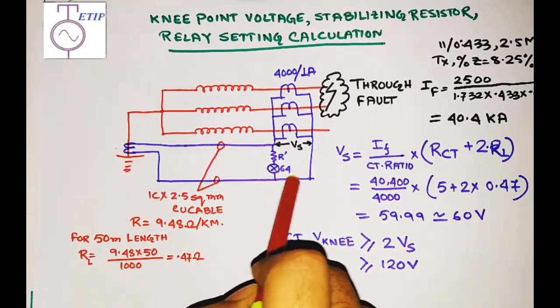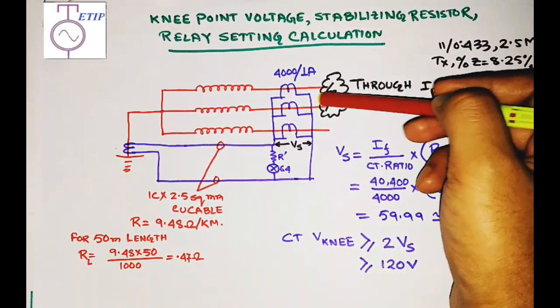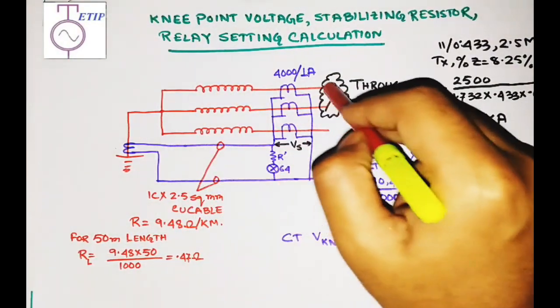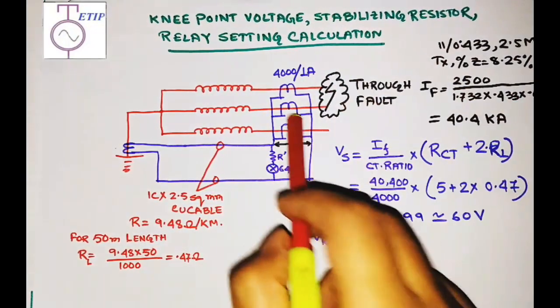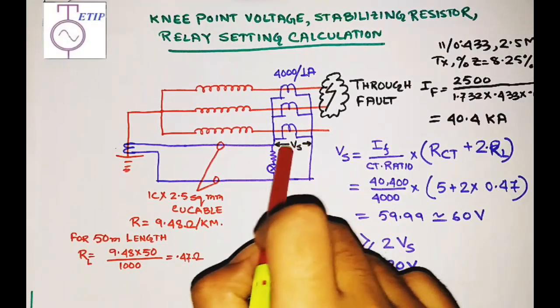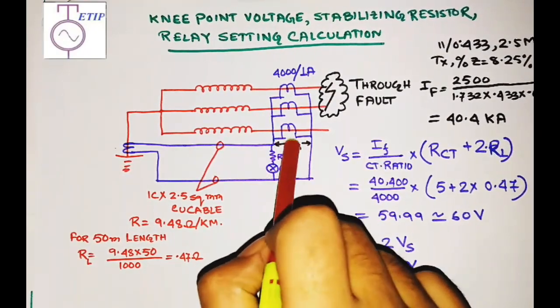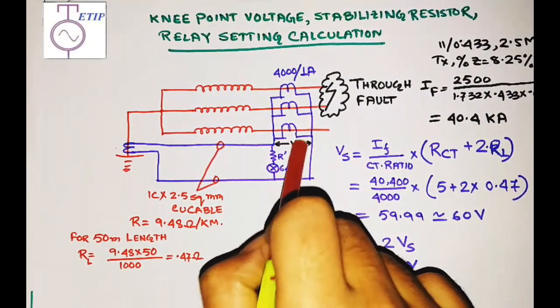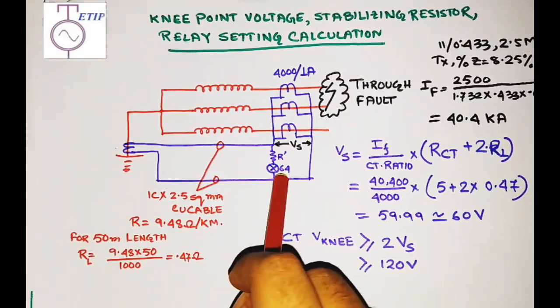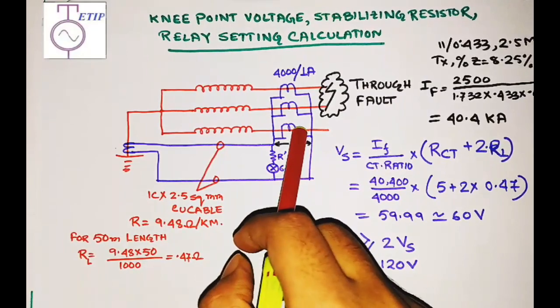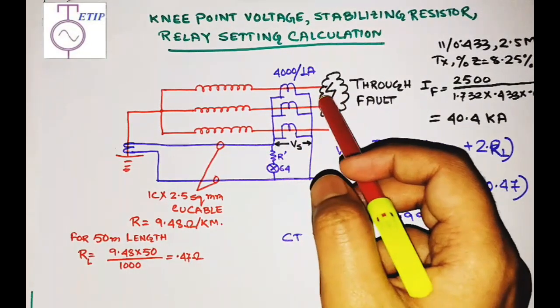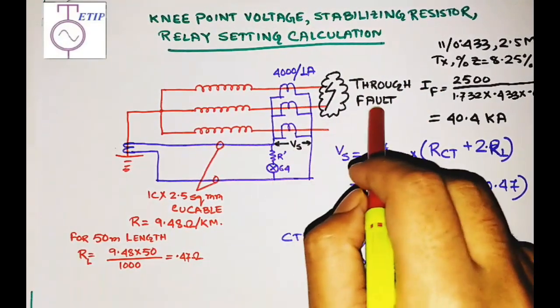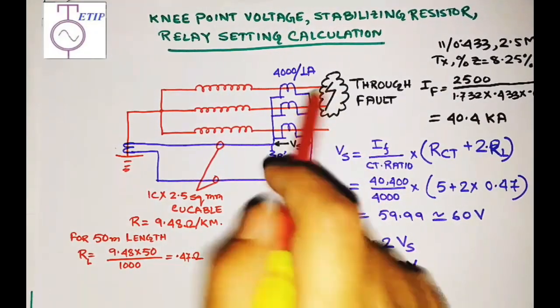Since all the CTs are connected in parallel, an equal voltage Vs will appear across all the CTs. Suppose a line-to-line through fault has occurred — current will try to drive through this relay coil, circulating in this path. This saturation voltage, or stabilizing voltage, will drive a current through the relay coil. If that current is higher than the relay pickup current, the relay will pick up, even though the fault is outside the protection zone. Our first objective is to prevent pickup of the relay for faults outside the zone.